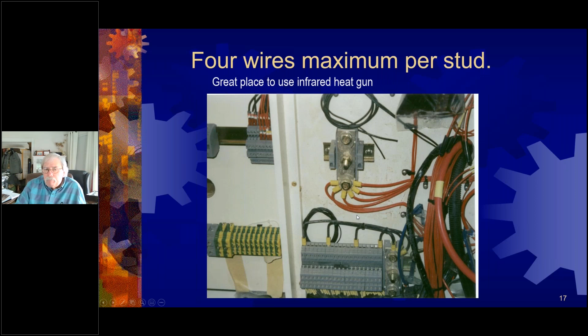The reason is properly fanning out the terminals to allow maximum contact, so that we don't end up with what in effect ends up being a loose connection that will generate heat. It just doesn't have the ampacity. We don't want screw type terminals bearing directly against our stranded cabling. This is a shot of an inverter.